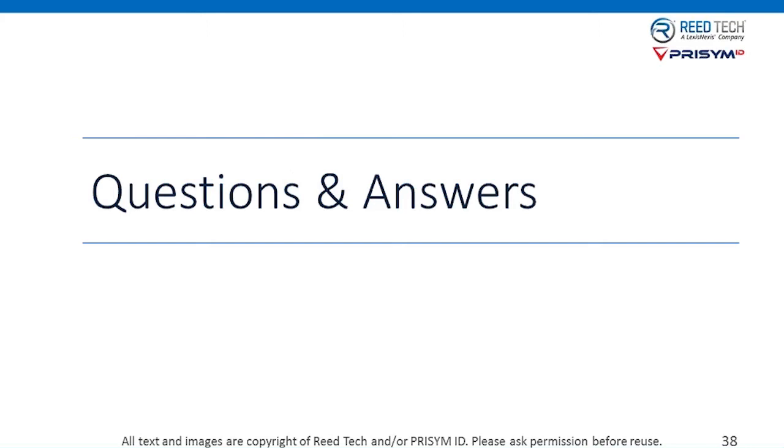If you think the validation process is a 2-month little cycle at the end, you may want to think again. It's going to be considerably longer. And it all depends on your validation plan. So securing your potential budget, your resources at an early stage, along with talking to your suppliers who you can leverage, should reduce your validation cycle and the time taken. So what you need to do, you need to plan for success, and that starts early.